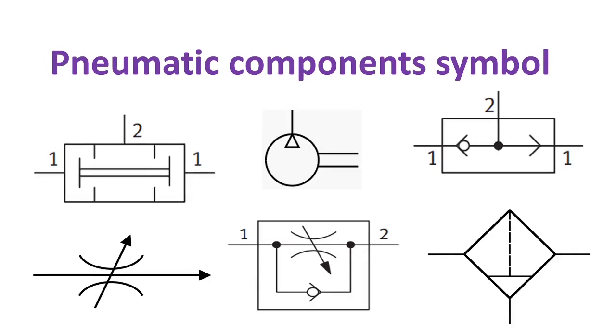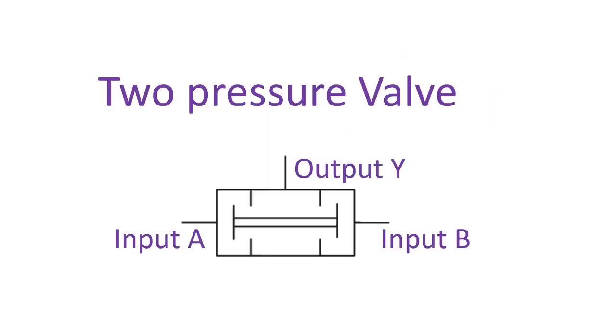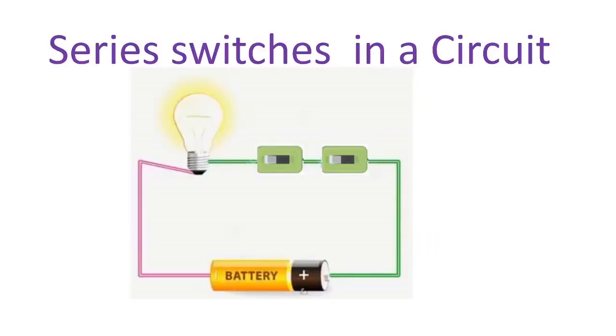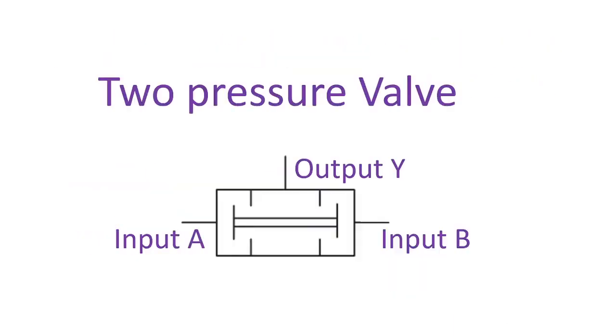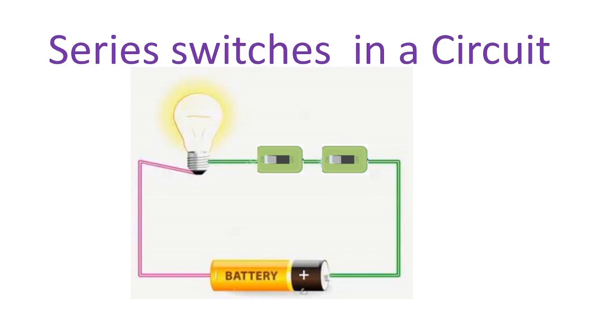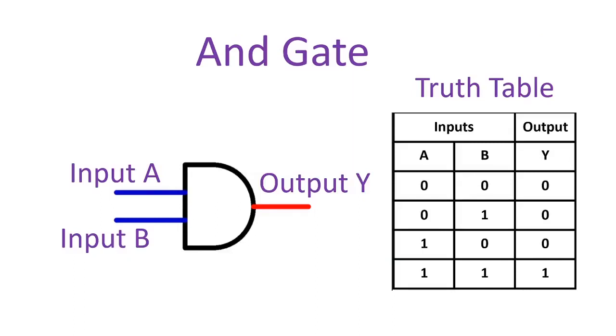Now let's proceed to pneumatic component symbols. The two-pressure valve works on the same principle as a series circuit and AND gate. The output of the two-pressure valve is true or high if both pressure inputs A and B are true, otherwise it's false. In the equivalent series circuit, the bulb will only glow if both switches are on. For the AND gate, it behaves according to the truth table — the output is 1 if both inputs A and B are 1, otherwise it's 0.